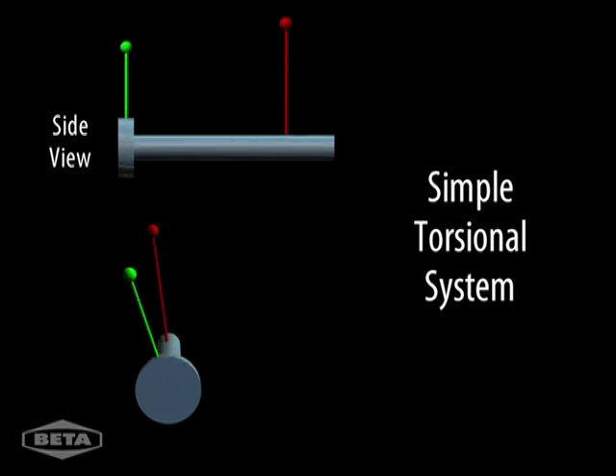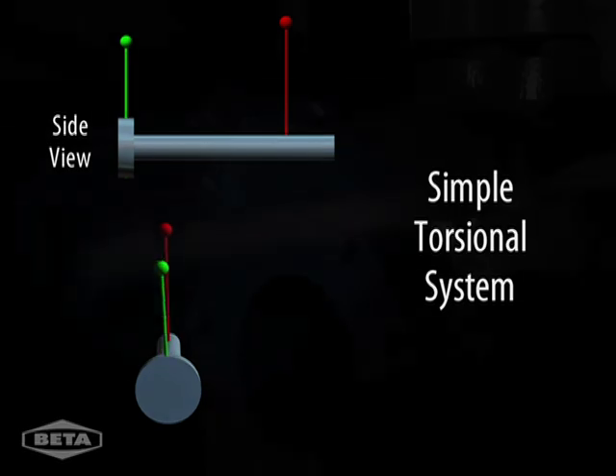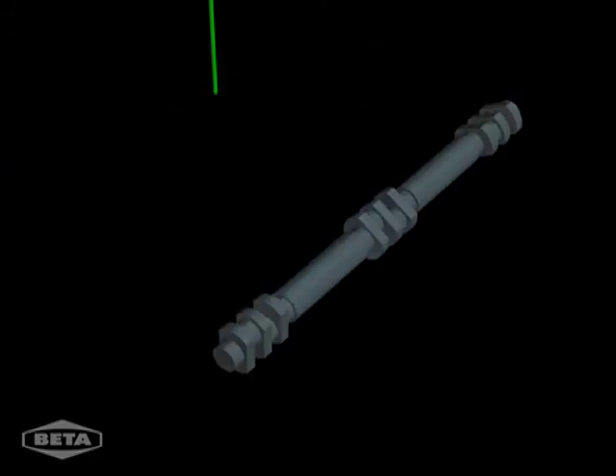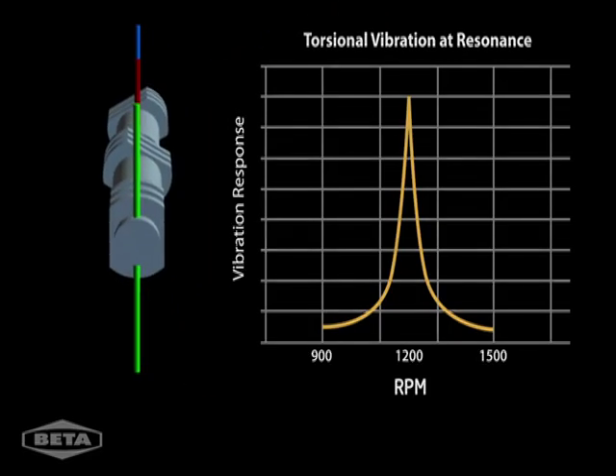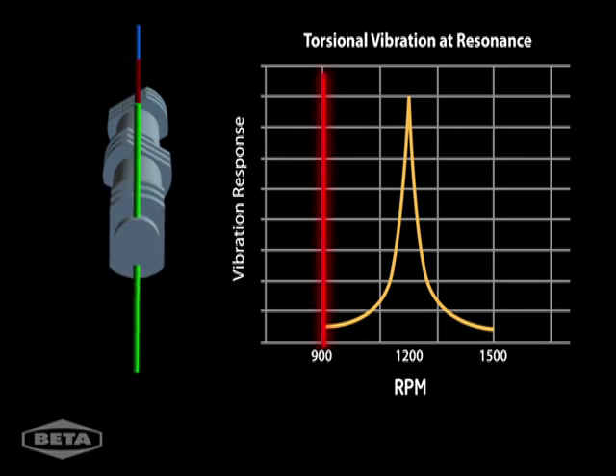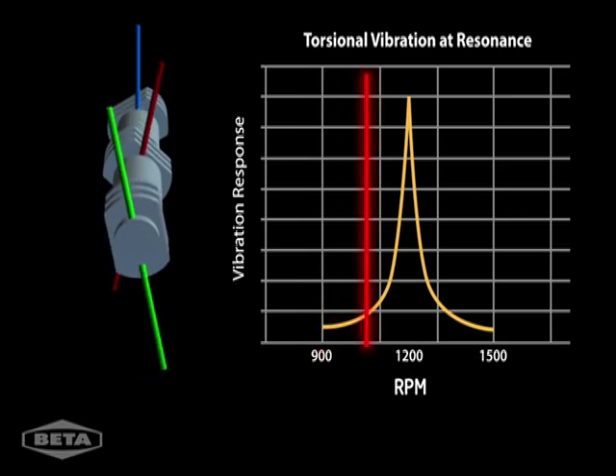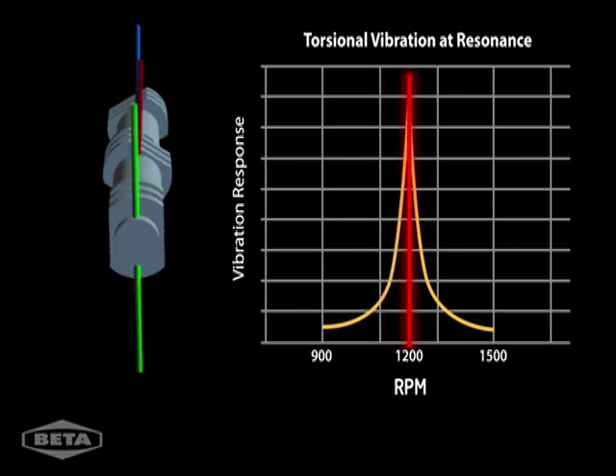After releasing the shaft, it rotates back and forth; this oscillation occurs at the torsional natural frequency. This is analogous to the mechanical natural frequency described in Module 1. Torsional vibration can occur especially if the system is resonant — in this example, the vibrations are low at 900 RPM, but as the speed increases, the system becomes resonant at 1200 RPM when the speed is at the TNF.